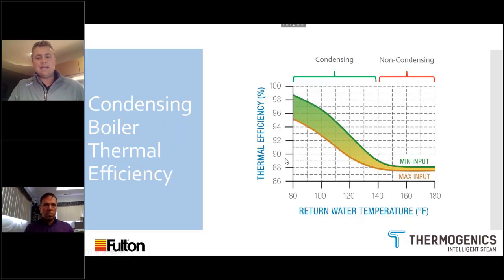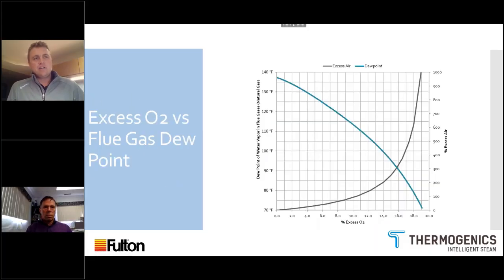So as you turn the boiler plant down and you get up in the firing rates, you translate to greater efficiency. But as you look at certain boiler types, and this goes for steam, but in particular in hot water as well, when you operate at lower firing rates, you actually introduce excess O2. So that's the air required for combustion. Depending on the boiler make and style, you require excess O2 to get the flue through the pressure drop of the vessel, but it's also to protect the burner from impingement of that flame and degradation against the boiler plate itself where the burner houses. But as you can see by this chart, as you change the amount of excess O2 in your burner, which typically occurs at lower firing rates, you actually reduce the point in which dew point occurs in the flue gas of natural gas.